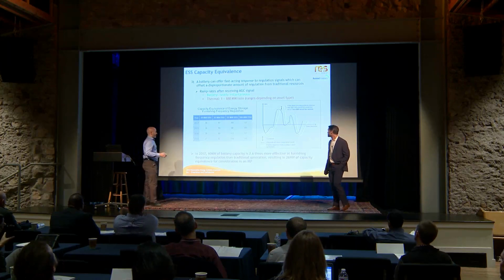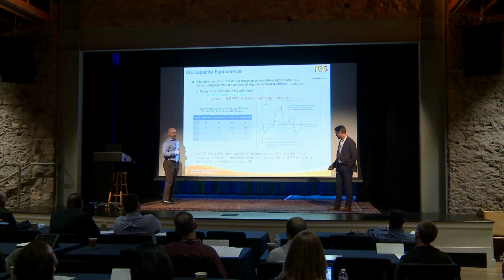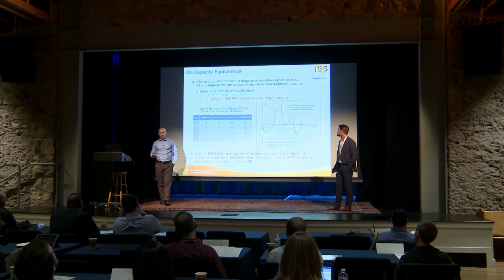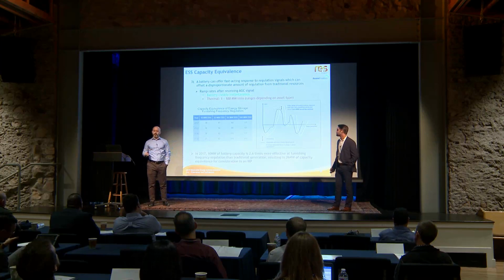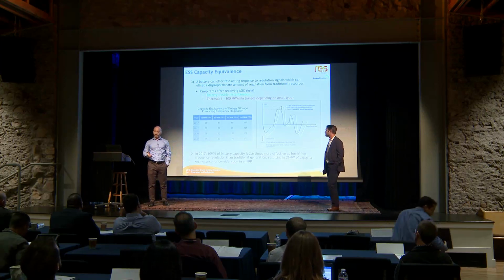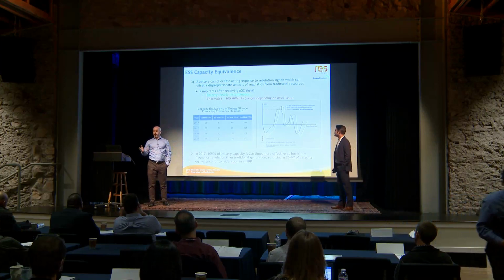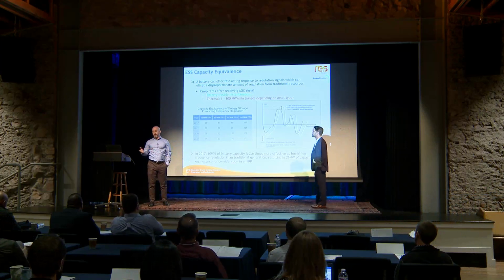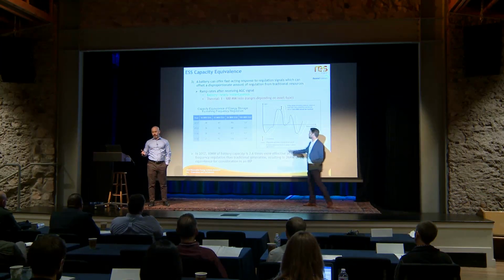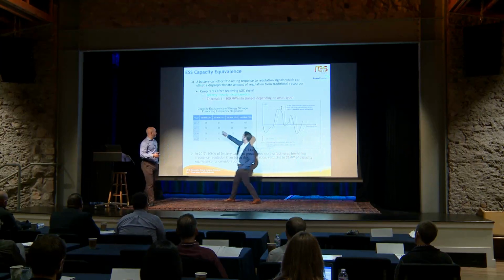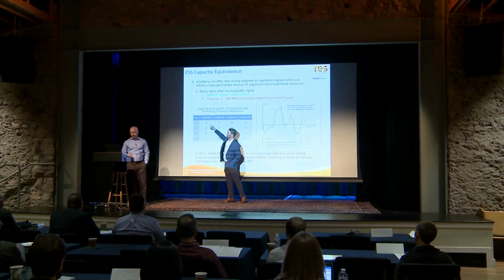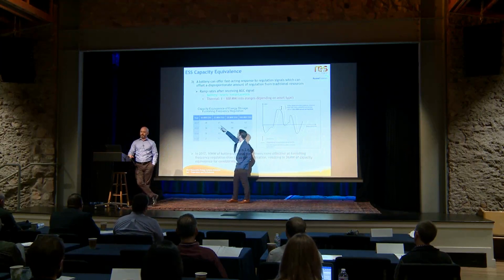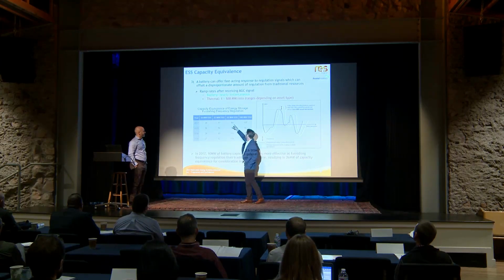This is also a case of diminishing returns. If I have 100 megawatts of regulation and put in a 10 megawatt battery, I get a very good multiplier. If I have 100 megawatts of regulation and put in a 100 megawatt battery, I don't get as good a multiplier. So you get the 2.6 times capacity equivalence if you have a 100 megawatt up requirement, but if you max that out at 50 megawatts, it's a much smaller benefit.